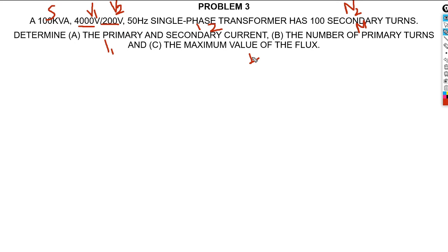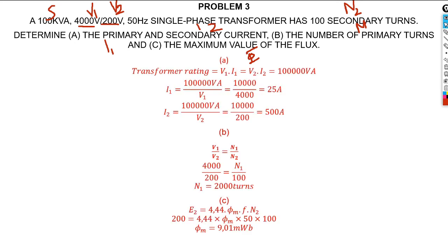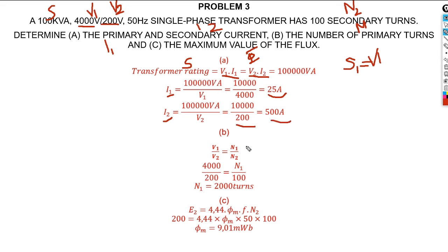We've already discussed how to use the turns ratio. From the transformer rating, S equals V1 times I1, which also equals V2 times I2. To find I1, take the rated power divided by V1 — that gives the primary current. For the secondary current, use the same rated power divided by V2. The kVA rating applies equally to both primary and secondary sides.